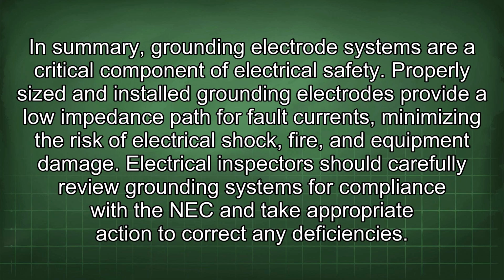In summary, grounding electrode systems are a critical component of electrical safety. Properly sized and installed grounding electrodes provide a low impedance path for fault currents, minimizing the risk of electrical shock, fire, and equipment damage. The electrical inspector should carefully review grounding systems for compliance with the NEC and take appropriate action to correct any deficiencies.